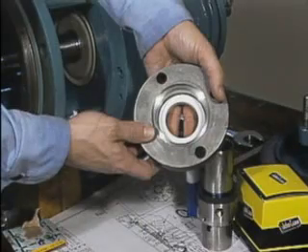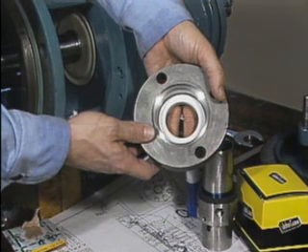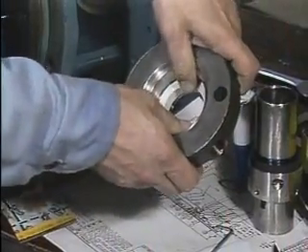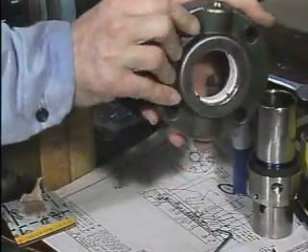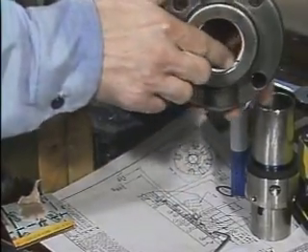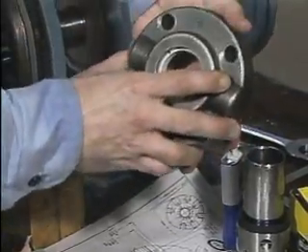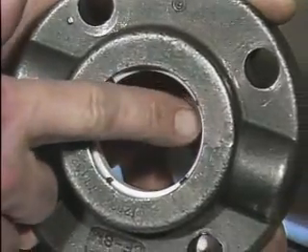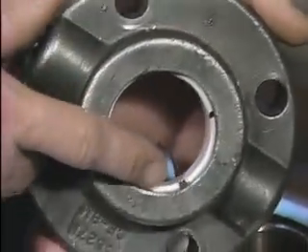Inserting the mating ring into the gland plate so that the unpolished side goes in first allows the polished side to face toward the rotating seal face when the rotating element is installed. The mating ring should be fully inserted into the gland plate, and it must not be cocked to either side. The gland plate can be turned over, and the back side of the ring can be checked to ensure that the ring is properly situated.